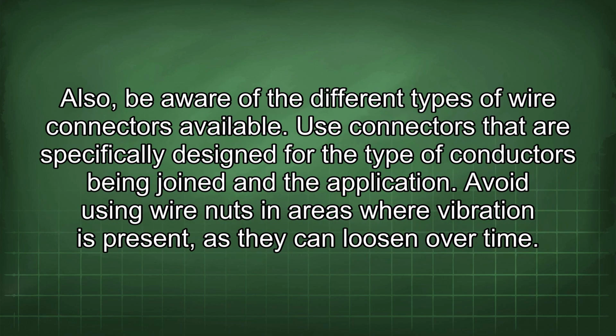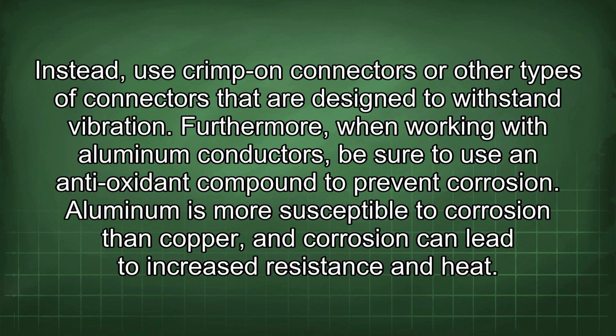Also, be aware of the different types of wire connectors available. Use connectors that are specifically designed for the type of conductors being joined and the application. Avoid using wire nuts in areas where vibration is present, as they can loosen over time. Instead, use crimp-on connectors or other types of connectors that are designed to withstand vibration.